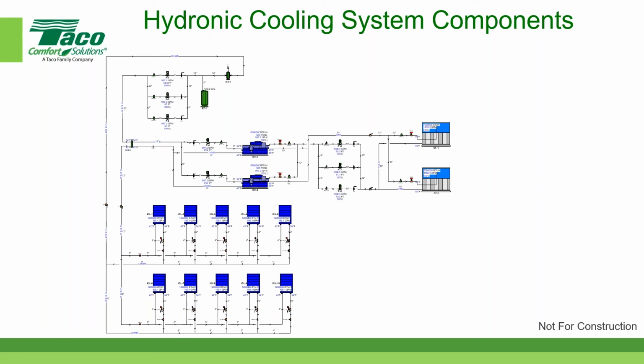Now, obviously, in tiny systems, it's probably not practical or cost-effective to use a centrifugal chiller. But we started off this discussion with buildings around 400,000 square feet. So anything between, say, 25,000 square feet and 1 million square feet, chilled water systems are extremely efficient and reliable. And I like to configure things the way I have them shown here. I like to have three pumps, each one sized for 50% of the design load. I like to have two chillers for 50%.